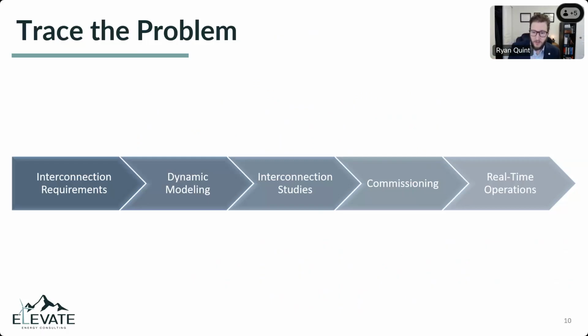What studies were done to make sure this resource can reliably ride through these events? Were the models used to run those studies adequate, sufficient, accurate, and did they adequately represent the controls and settings within that facility? And are there fundamentally even requirements that exist saying this facility must ride through this event? The answer has historically been no, except in a couple areas. So we have to shore up notable gaps in this whole process if we expect reliable operation of these IBR facilities through these grid events.